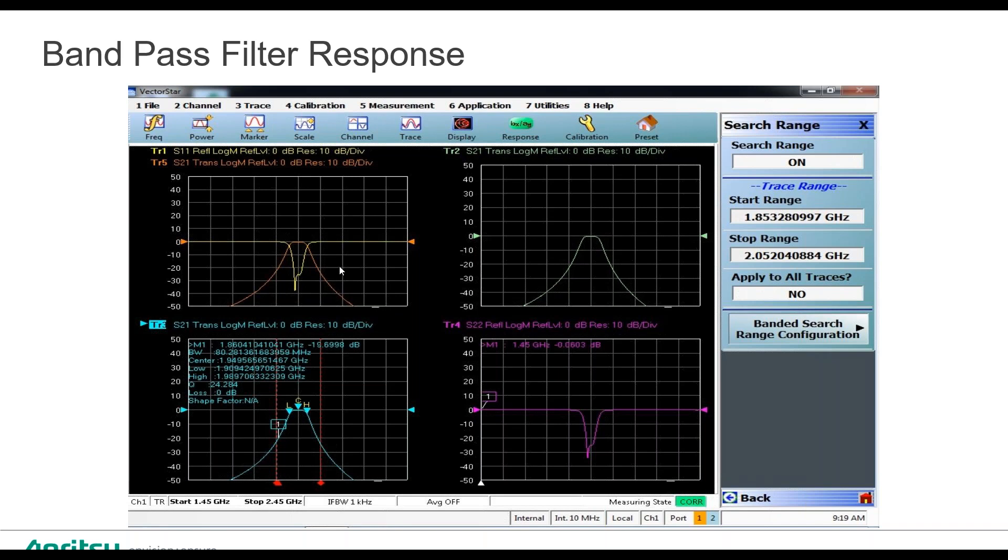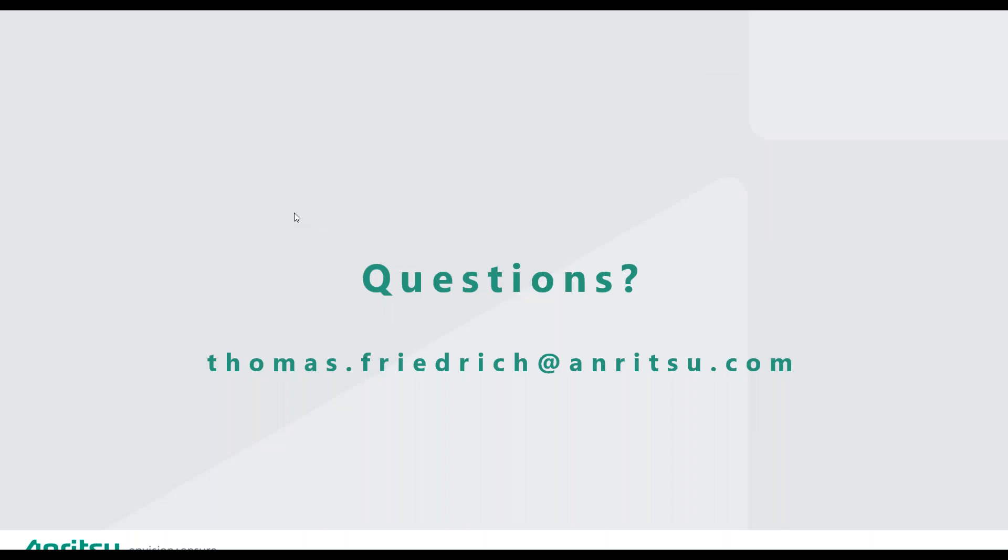Thank you. Next question. Do all ANRITSU VNAs have the Q-bandwidth measurement capability, and is it an option or standard? They all do. All of the benchtop models will have the shape factor, Q-factor, those types of statistics as well. And I'll bring up a VNA display here in a second. Those are standard. They're not an option, so they're in every benchtop model that ANRITSU has.